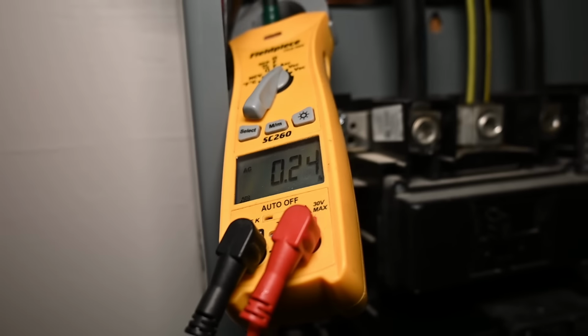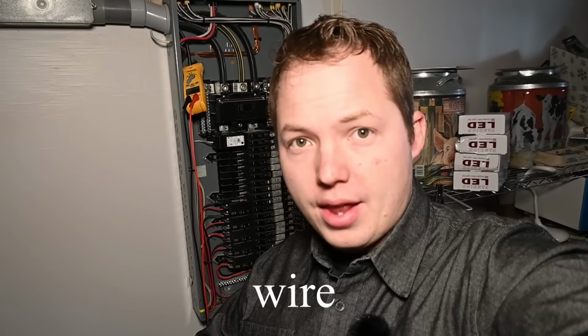0.24 amps. I do not understand this. There's still the same amount of current going through that ground rod as when the entire system was energized. We have the main breaker turned off outside that feeds this panel, and every single breaker turned off inside this panel and the one out there. And we are still getting current flowing through that wire.